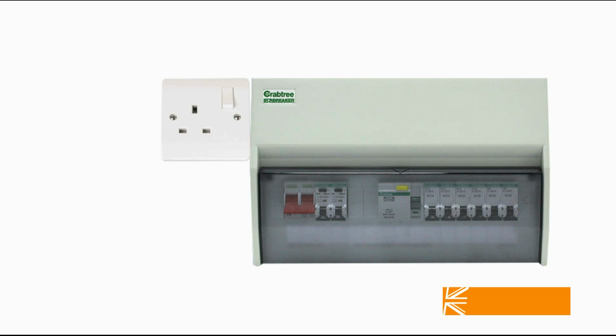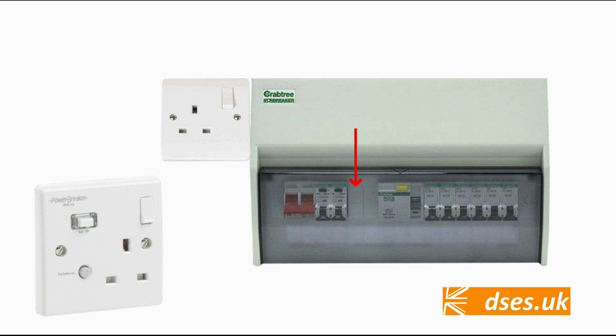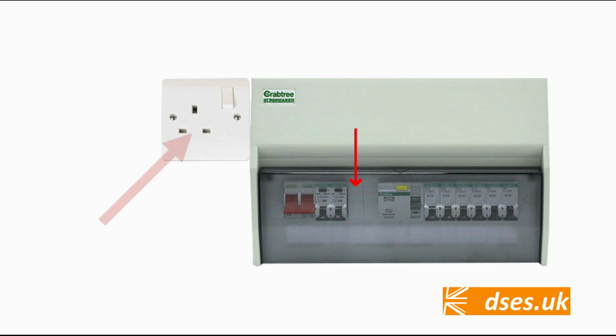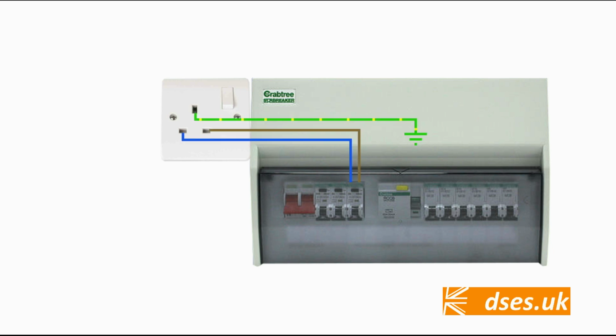I could install an ordinary 16 amp breaker into one of those spare ways and put in an RCD equipped outlet. Or I could install a 16 amp RCBO in one of those spare ways and put in an ordinary outlet. Those last two options may cost a little more in materials, but ought to be less faff, as I wouldn't be having to check and take on the responsibility for any existing circuits, and besides, junctioning into the existing wiring may be fiddly. However, if I do utilise one of the spare circuit ways, this becomes a wholly new circuit, albeit a very short one serving only one point.